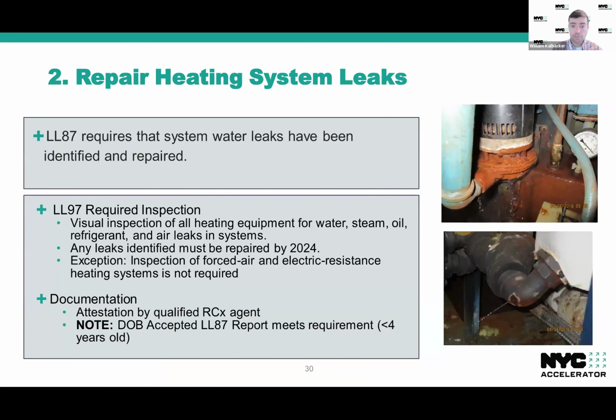The specific Local Law 87 requirement is pretty much a one-to-one match. It's that steam and system hot water leaks have been identified and repaired. Specifically for Local Law 97 inspection requirements, the RCX agent has to visually inspect the equipment, make sure that there are no leaks, and if leaks are found, they have to be repaired and documented. Again, the exception being for forced air and electric resistance systems, those are exempt. Documentation, very similar to the first measure. You have to have an attestation from an RCX agent, but a Local Law 87 energy audit from the last 4 years is also sufficient to meet the requirement.